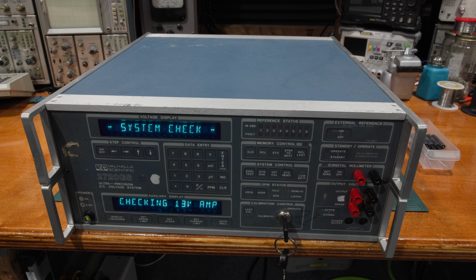And we'll check the amps. Why not? Yes, we do want to check the reference system. This should bring back reference 6. It's odd that reference 6 dropped out. All right, reference 6 is back, but reference 5 is probably going to be out of range, which is okay. That gets us back to 0. Yep, 5 is faulty. 6 is being used. All right, cool. 7 and 8 don't exist.